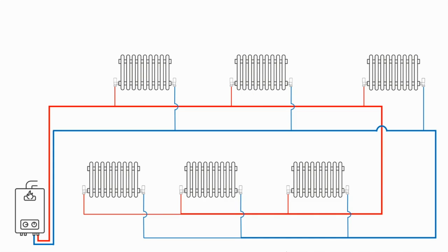Here we have a scenario where the system is out of balance. This first radiator hasn't been balanced, so the valves are wide open. As the hot water leaves the boiler and approaches the T, it now finds that the path of least resistance is to go through the radiator. Therefore, it doesn't allow the water to flow on to the rest of the radiators on the system.